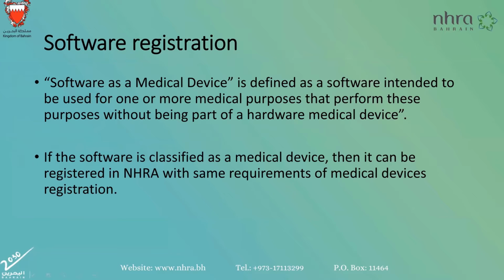As part of the updates to the guideline, there are also some new sections or topics addressed that were not covered in the previous guideline. The first topic is software as a medical device registration. Software as a medical device is defined as software intended to be used for one or more medical purposes that performs these purposes without being part of a hardware medical device. So a software with a medical purpose that operates on a general purpose device or platform is a software as a medical device. A general purpose platform and device could be, for example, iOS on an iPhone. So having software on that device for a medical purpose is a software as a medical device.